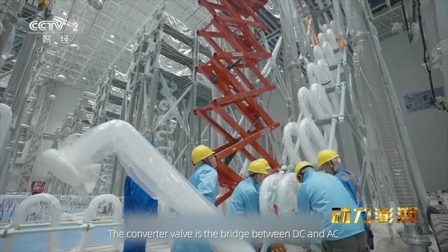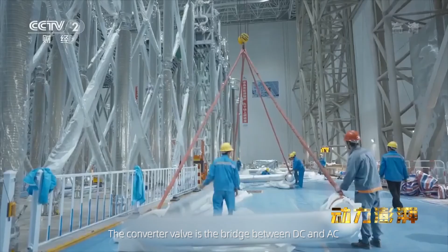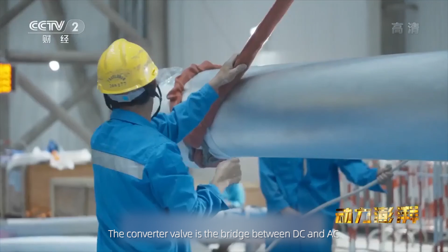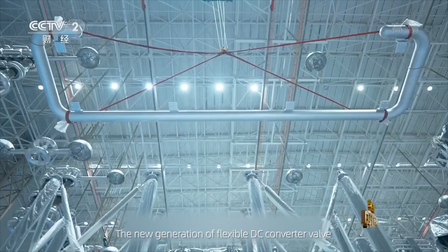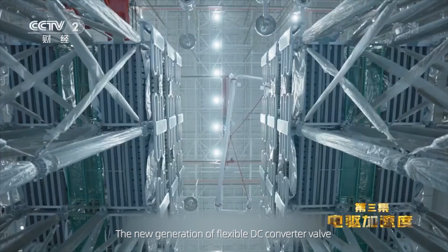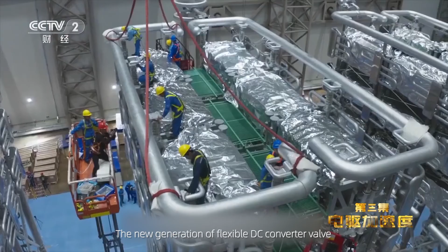The converter valve is the bridge between DC and AC. The new generation of flexible DC converter valve has a faster power regulation speed. It is possible to quickly compensate for the fluctuating clean energy charge and power, turning the aggressive and unruly currents into softness, making it possible to connect clean energy to the grid. At the same time, it can shorten the grid troubleshooting time to less than 100 milliseconds, just like installing a dam with an intelligent brain in a river that is flooded with water. Precisely controls the direction and size of the power tide to support safe and stable operation of the grid. And the secret to achieving this function is hidden here.